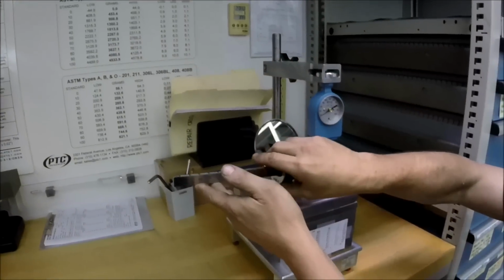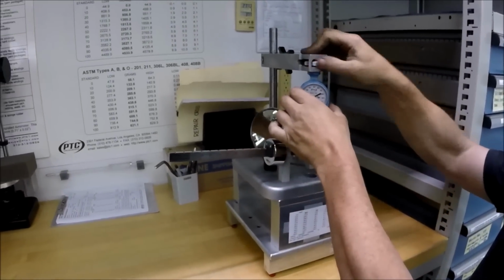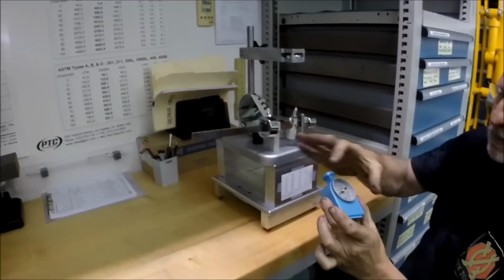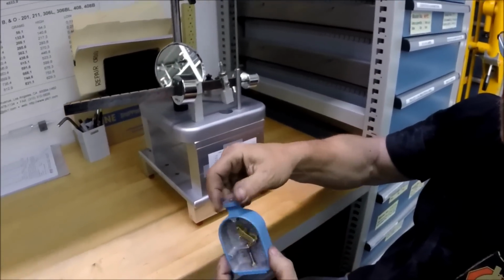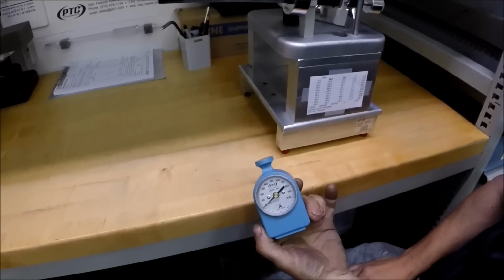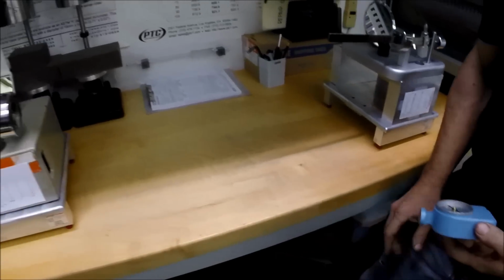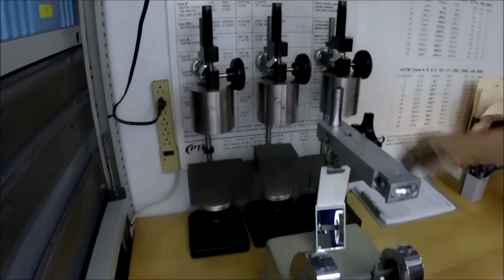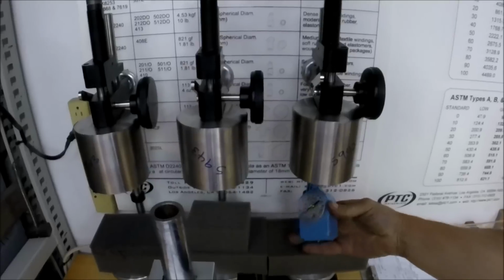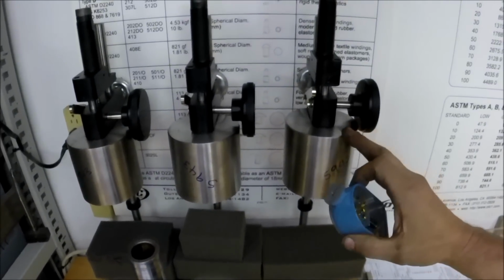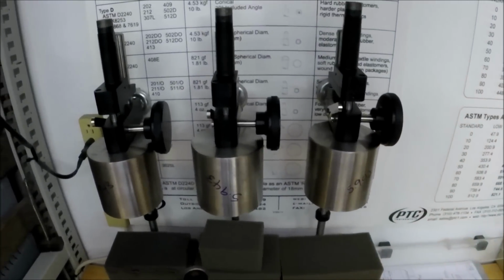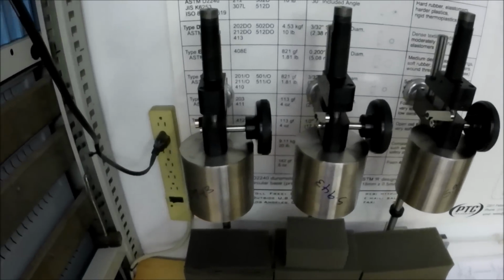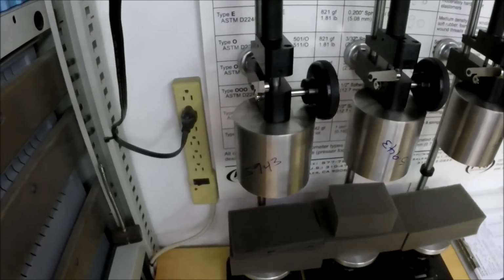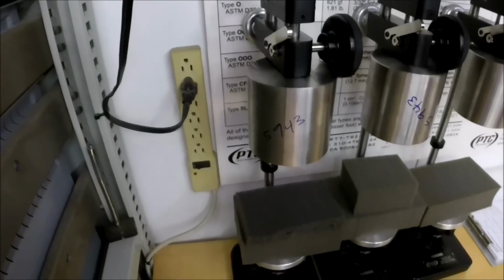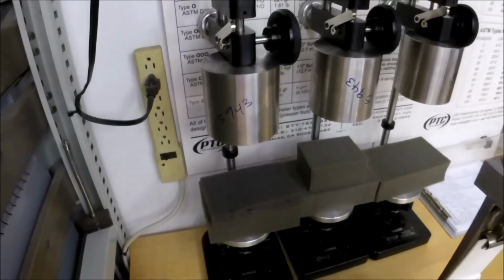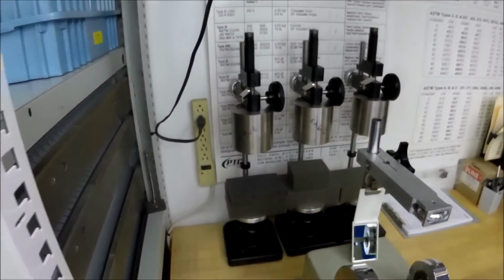From this point, once they're calibrated, they will get the cover glass, a ring, a back piece, and become a complete instrument. These are test stands that can be used to hold an instrument to remove the operator error, so that it applies the same amount of force each and every test. So for companies looking for much more repetitive testing, a durometer stand is usually the way to eliminate the operator error.